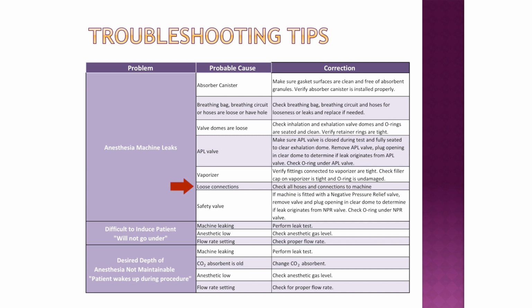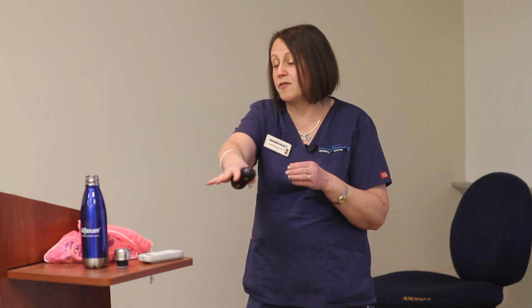Make sure there's not a loose connection. Like when we were checking for leaks, we were using one of the F circuits that had a crack right on the short section of hose that I used to do my leak test, and that's how we found a 1 liter leak.